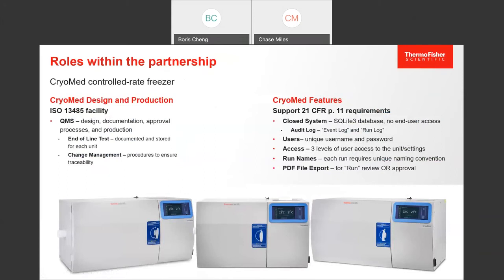Focusing specifically on the Cryomed control rate freezer and its role within this partnership, on the left-hand side, we know now it's an ISO 13485 facility with a QMS system that's also driving end-of-line test and change management processes. That's on the building side. That's our process side. However, the Cryomed contains features that support 21 CFR Part 11, as we've discussed, by having a closed system with an SQL database. There is no end user access. Members of the XYZ Cell Therapy Company cannot go in and query and access this database, and they cannot manipulate or change data within it. Once data is created, it's locked into the machine.